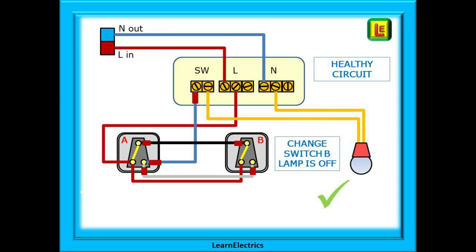Now, change switch B over this time. The circuit is the same up to switch B. But now, because the switch contacts have moved, it leaves switch B on the brown wire. The brown wire joins the first brown wire at switch A. Then the electric goes off to switch B again and back out on the brown wire. It is caught in a loop and cannot make the jump to the blue wire in switch A, so the lamp will be off.